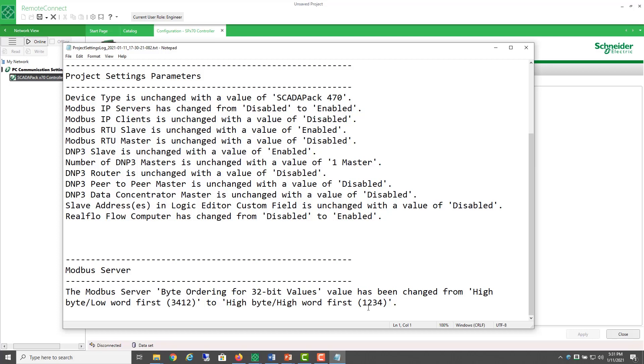When Realflo configuration software uses Modbus to share 32-bit values with SCADA pack flow computers, it has always used this byte order 1234 for this data. Some users may recall that Telepace SCADA packs also use this 32-bit byte order of 1234.